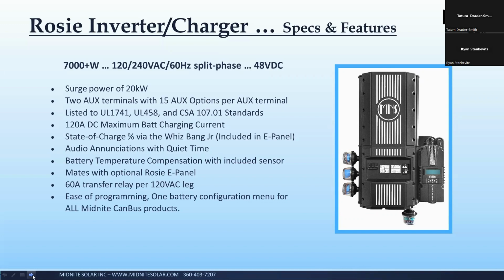Some of the other neat things about the Rosie: it does have 2 auxiliary terminals, 15 or so different auxiliary options, things like diversion, vent fan. There's also inputs for things like a light switch application. So if you're putting this in a cabin where you want to turn it off when you leave, you don't have to go to the Rosie. You can flip a light switch or force things like EQ or float by a contact closure. A lot of different functionality there.